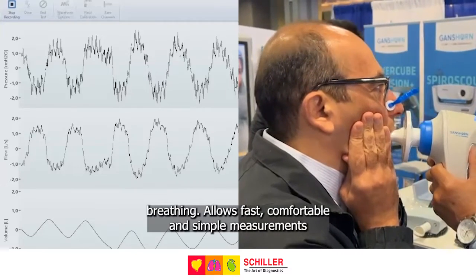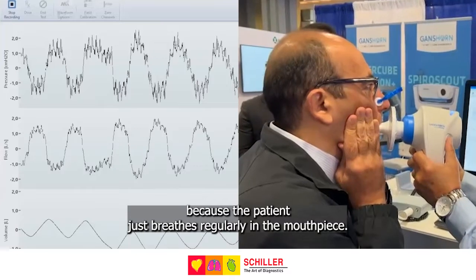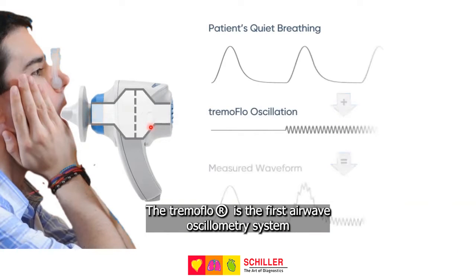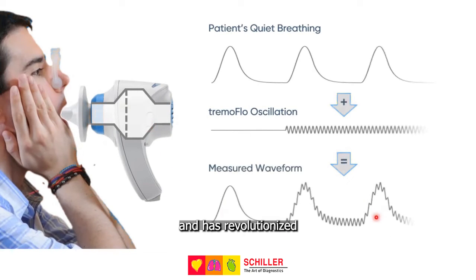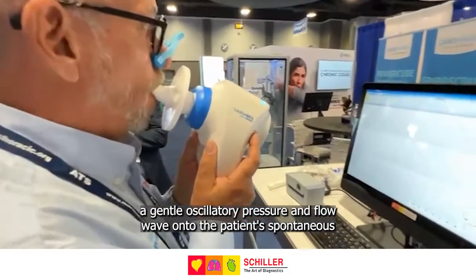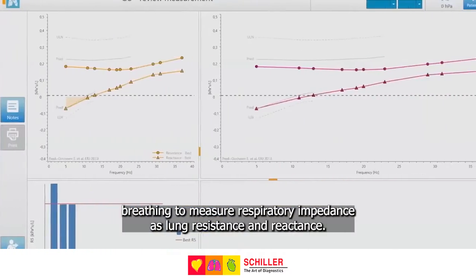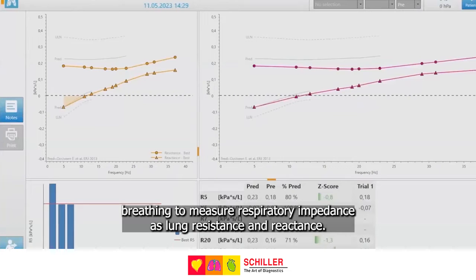It allows fast, comfortable, and simple measurements because the patient just breathes regularly into the mouthpiece. The tremoflo is the first airwave oscillometry system and has revolutionized the forced oscillation technique by using a vibrating mesh to superimpose a gentle oscillatory pressure and flow wave onto the patient's spontaneous breathing to measure respiratory impedance as lung resistance and reactance.